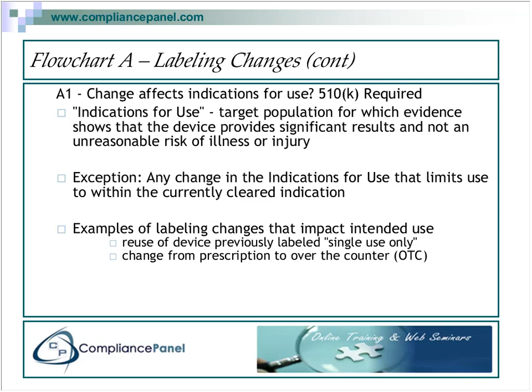And lastly, is the labeling being revised for clarity to ensure safer or more effective use? If it is, no 510K is required. What you're doing here is your firm realizes that you want to make the device easier or safer or more effective to use, or just, there's something you want to clarify. The FDA doesn't want you to stop doing that, submit a 510K, then go ahead, wait 90 days. They want people and end users to know that your device should be used in a safer manner immediately.